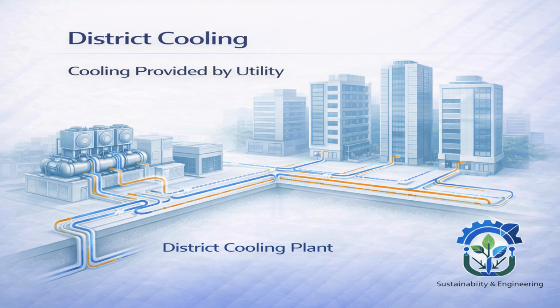Now let's move to a system that is very common in UAE and the Middle East. That is district cooling. District cooling is fundamentally different from everything we have discussed so far. Here, the building does not produce its own cooling. Instead, cooling is generated by a central utility plant and supplied to multiple buildings through an underground chill water network. So from the building point of view, there are no chillers, no cooling towers, no large mechanical plants. The building simply receives chill water from the utility.